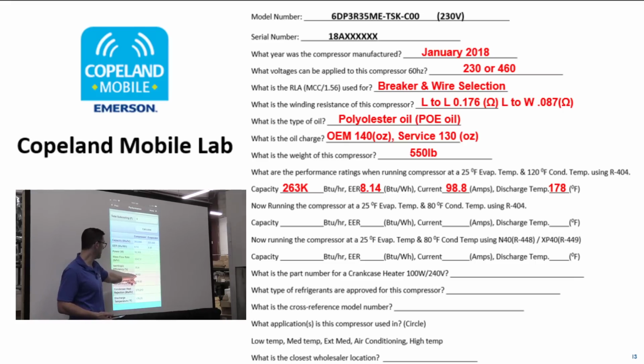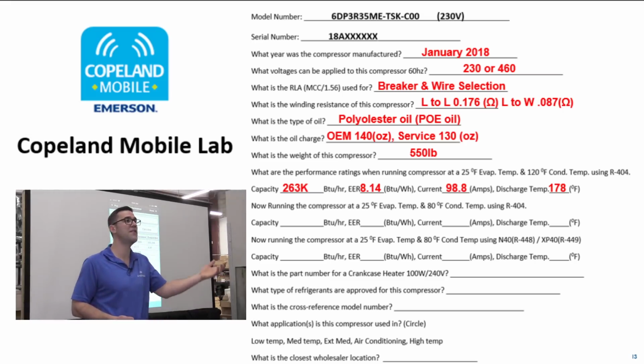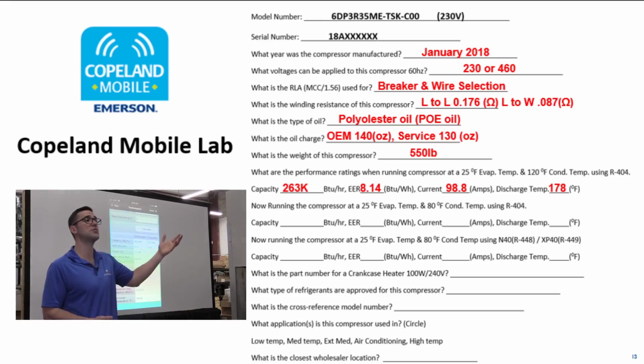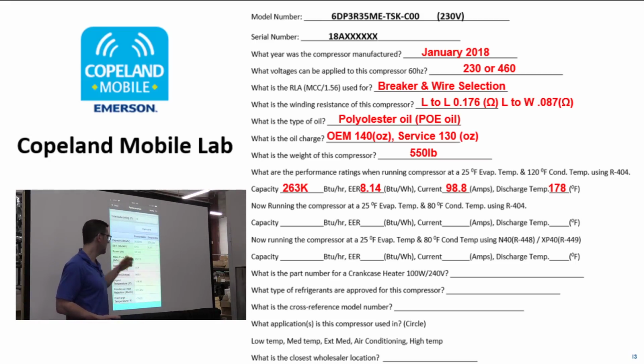If you all of a sudden get a way higher amps, what could that be? Just say it's supposed to be 98 and you're getting 110 or 105. High load. Plugged condenser, who knows what it could be? It could be one of many things, but it should make you think as a technician, well, this is what it should be. Okay? So, I just want to show you this. This is 263 and 98 at 25 evaporating and 120 condensing.